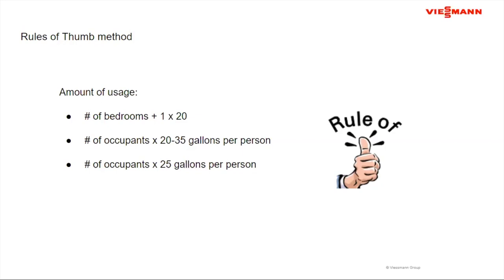The bedroom one is the one I tend to use, where you take the number of bedrooms, you add one to that number, and you multiply by 20. So for instance, we have a four-bedroom house. Four bedrooms plus one makes it five. Five times 20, I'm going to say, rule of thumb number, I'm probably going to need about 100 gallons first hour recovery. Okay. Now down here, number of occupants times 20 to 35 gallons per person. Four bedroom house, married couple, three kids, that's five people. That's somewhere close to 100 gallons as well.